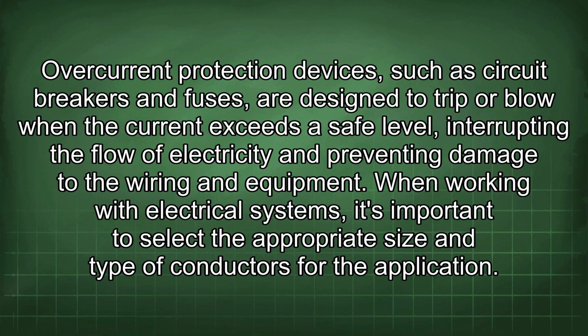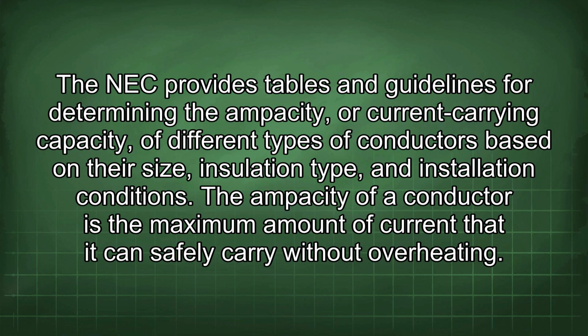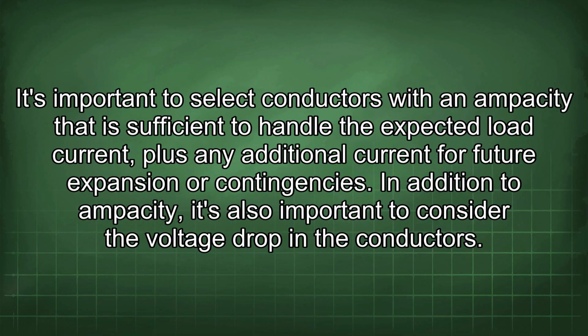When working with electrical systems, it's important to select the appropriate size and type of conductors for the application. The NEC provides tables and guidelines for determining the ampacity, or current carrying capacity, of different types of conductors based on their size, insulation type, and installation conditions. The ampacity of a conductor is the maximum amount of current that it can safely carry without overheating. It's important to select conductors with an ampacity that is sufficient to handle the expected load current, plus any additional current for future expansion or contingencies.